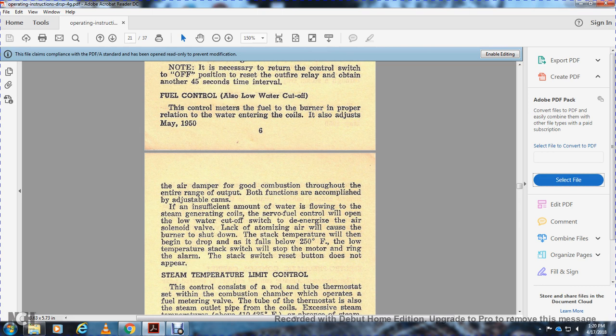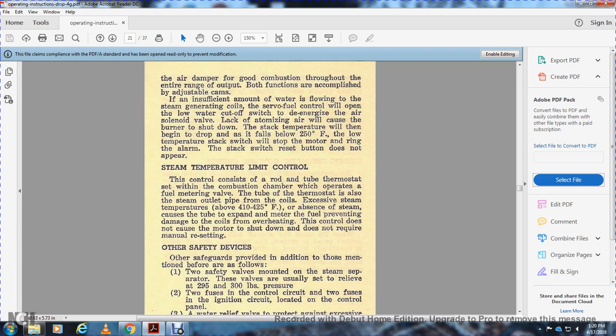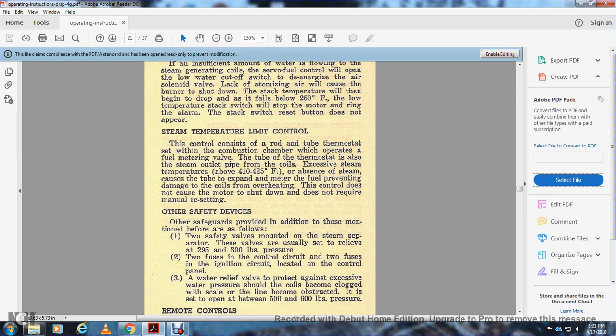The steam temperature will then begin to drop and as it falls below 250 degrees. The low temperature stack switch will stop the motor and ring the alarm. The stack switch reset button does not appear. Steam temperature is limited by the control, which consists of a tube thermostat within the combustion chamber. It operates the fuel meter valve, and the thermostat is also the steam outlet pipe from the coil when the steam temperature is above 410 to 425 degrees Fahrenheit. Absence of steam causes the tube to expand and meter the fuel, preventing overheating as it cools. The control does not cause the motor to shut down and does not require manual resetting.